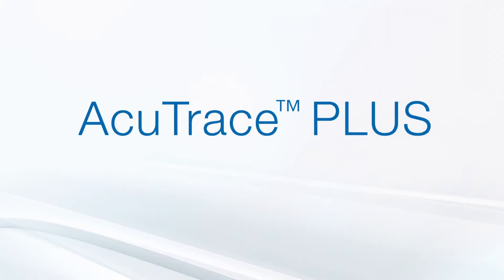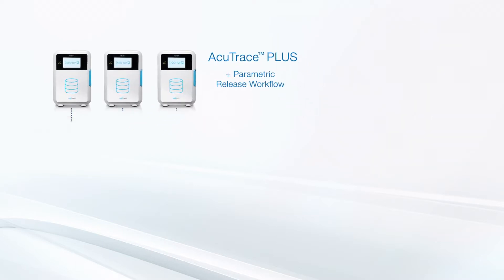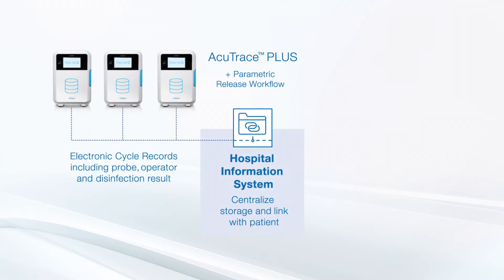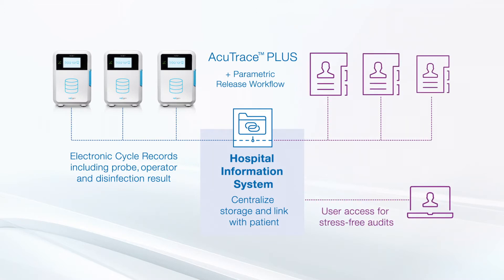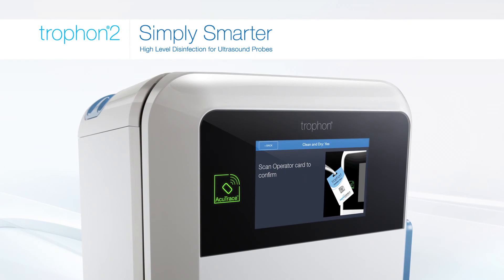If you have activated the optional AcuTrace Plus software, your trophon2 can be integrated with the hospital IT system, allowing all disinfection cycles to be stored, accessed, and easily linked to a patient's electronic medical record. trophon is simply smarter high-level disinfection for ultrasound probe reprocessing.